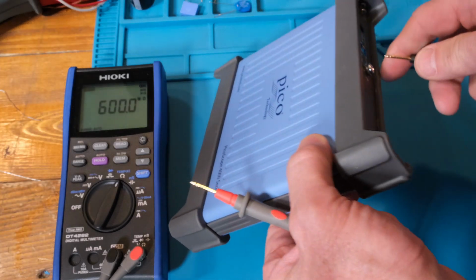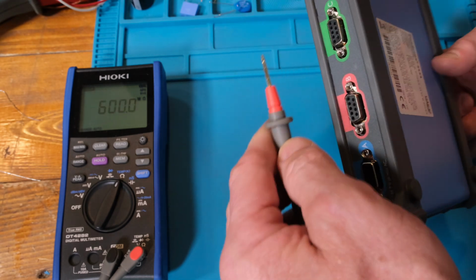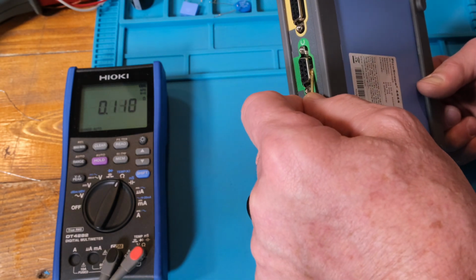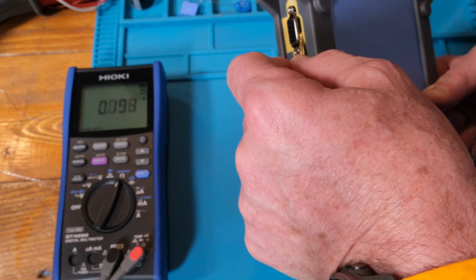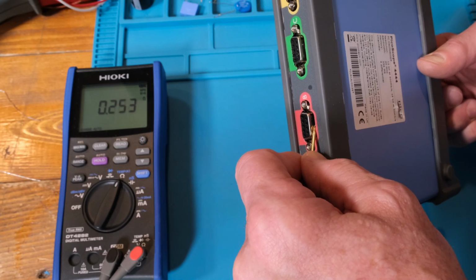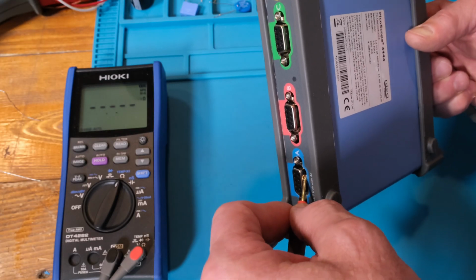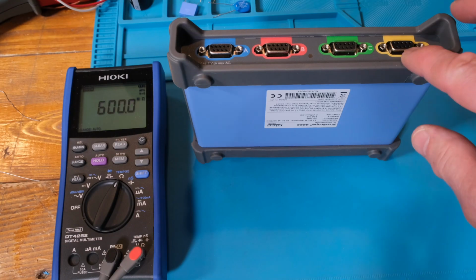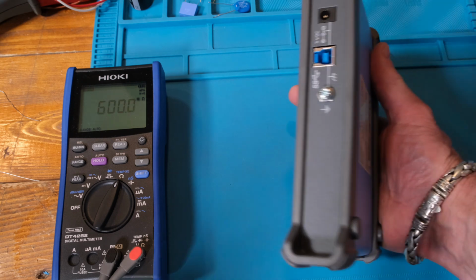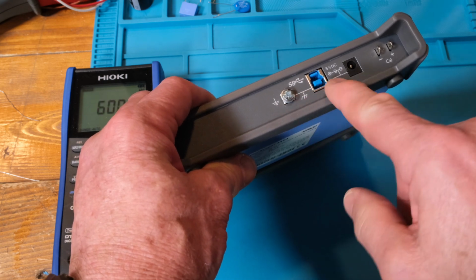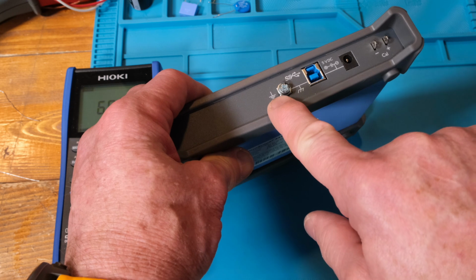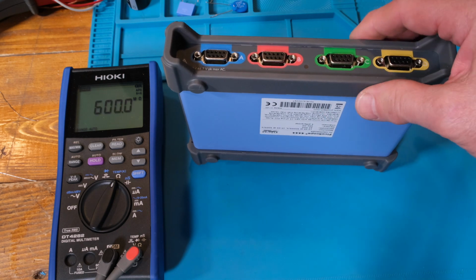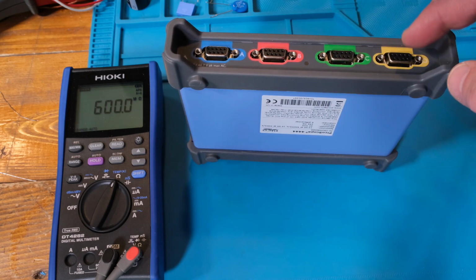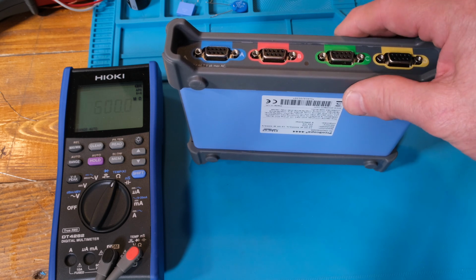Okay, so just take that a little bit further. If I come over here to the minus, to the chassis connection, and touch the shields here, it looks like the shields in front are all tied to chassis. So if you want those shields tied to chassis, then you tie that thing to chassis. So yeah, it looks like all your shields for your cables are tied to the chassis, which is all those shields which you would tie to earth ground, your protective earth ground. But again, that's just your shields being tied. Your input connections are still essentially isolated, as differential probes.